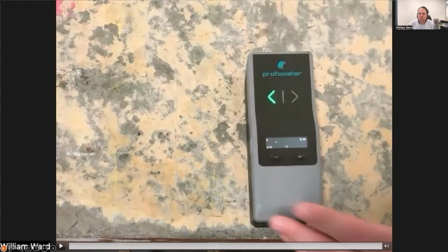So the calibration means the machine is the same as all other machines. The development of the machine means the machine is able to measure accurately. And then your verification and checks on site are what you do if you need full confidence that today's measurement is valid and useful. If you look at some of the processes used by coating inspectors, by people in metal ultrasound, a lot of their process is to use test blocks or proxies to adjust the settings of their devices to measure as precisely as they can. It's the same thing with the use of a cover meter. The more critical the measurements, the more important it is to have an understanding of how it's behaving today.